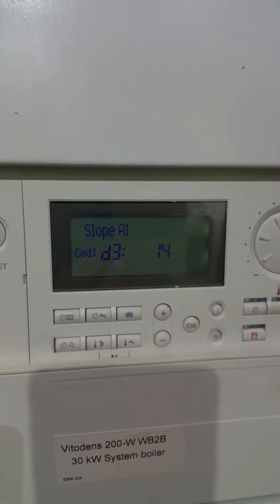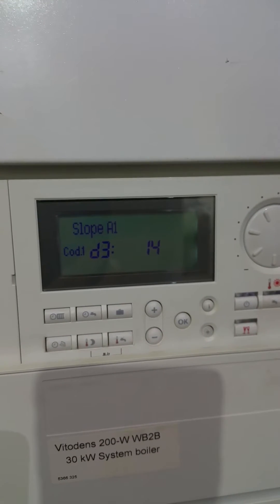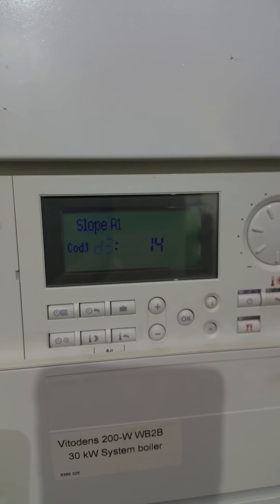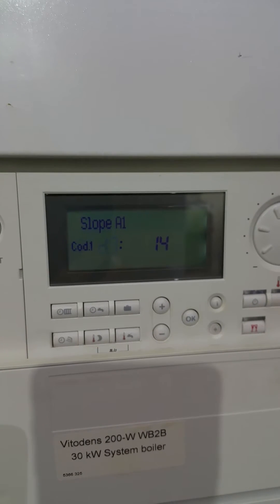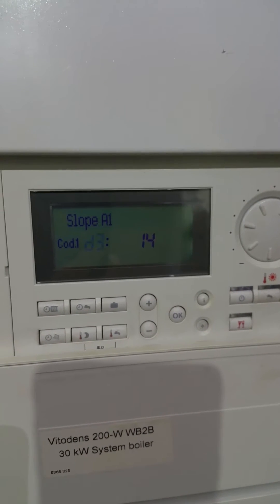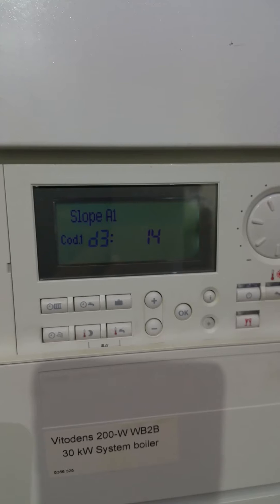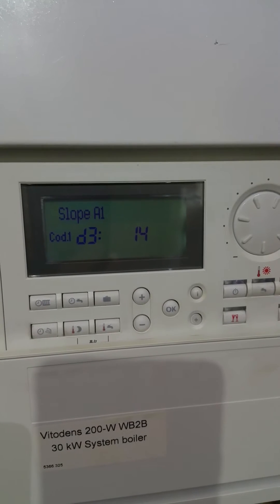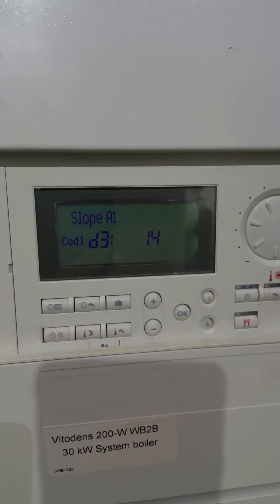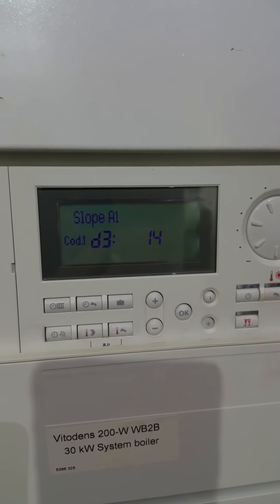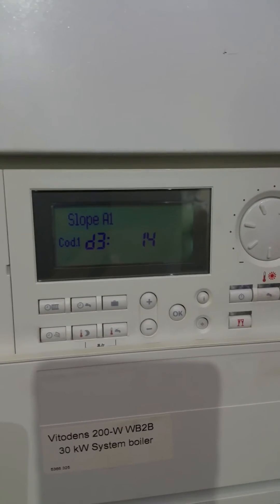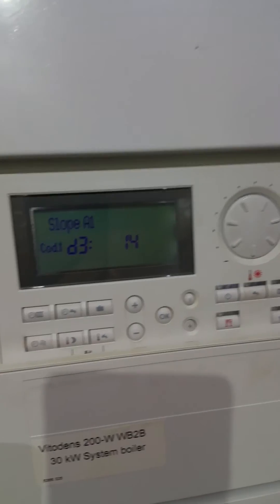If you've got the boiler set at a specific temperature and the rooms aren't reaching that temperature, it suggests that the curve is low and you need to raise it. If you've got it set at a specific temperature and the rooms are running at a higher temperature, it suggests the curve is too high and you need to lower it.